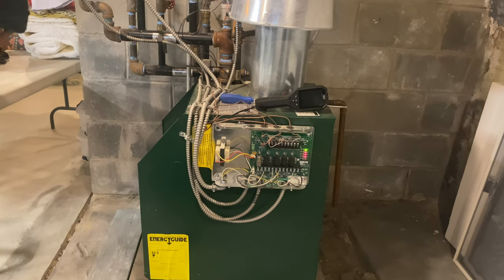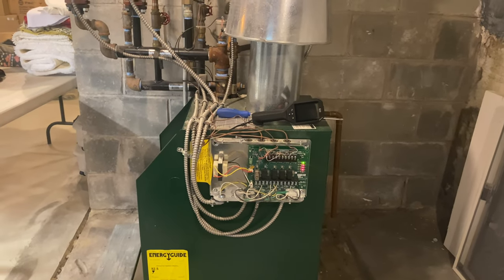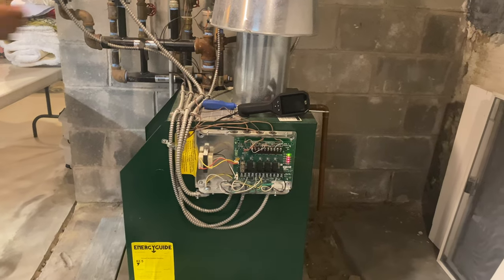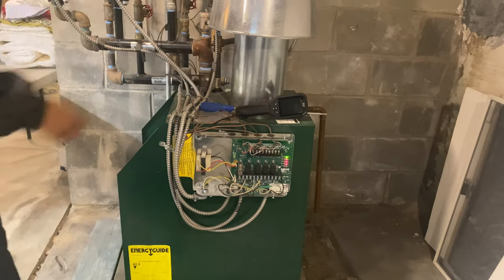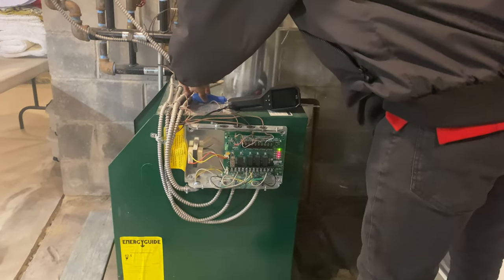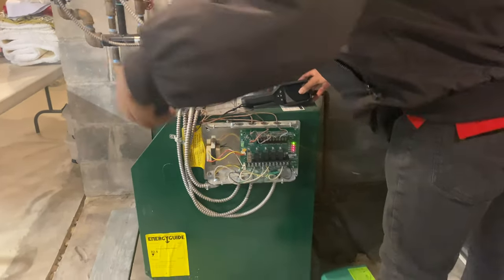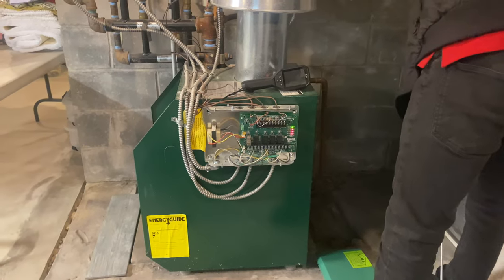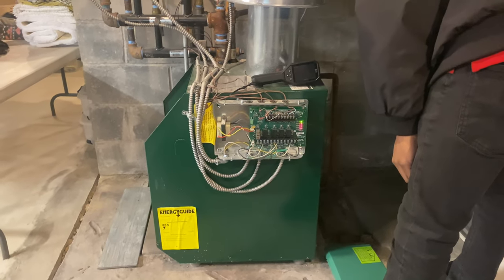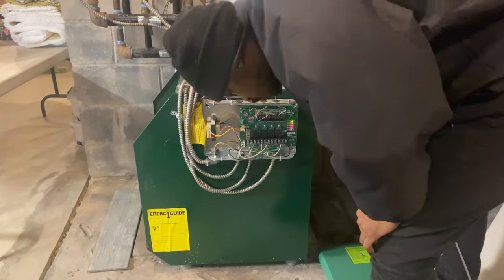But let's say it's 50 degrees out, and the thermostat is on, it doesn't need that 180 degrees of water. It needs 145, 150. You also have to consider there are limitations on how low you can go with this type of boiler. If you had a wall-hung system, you can go down to 110 and it'll thrive, like it's designed for that.